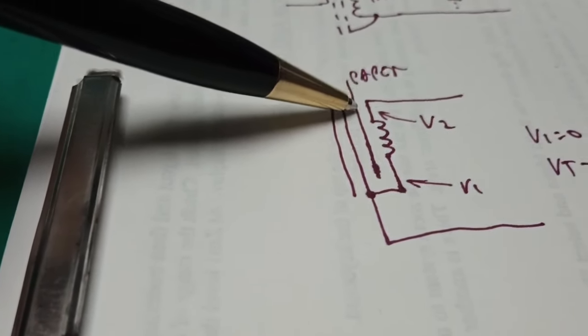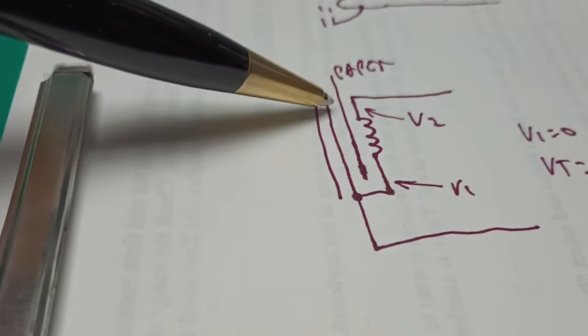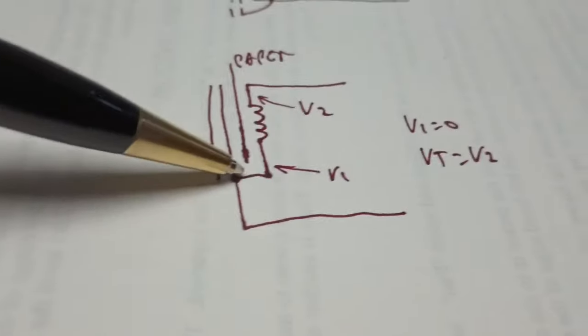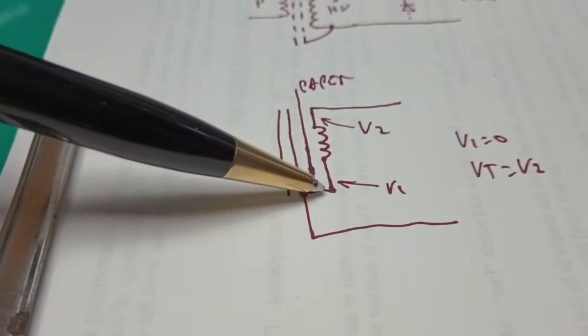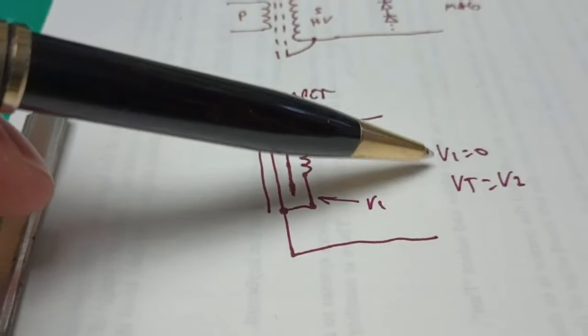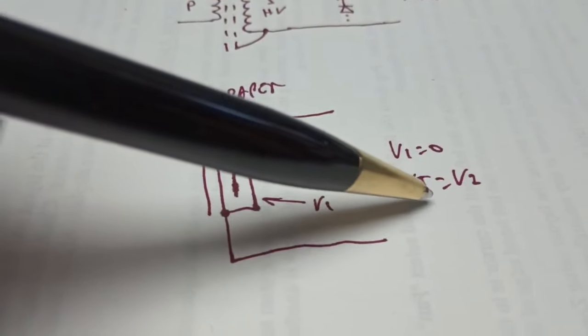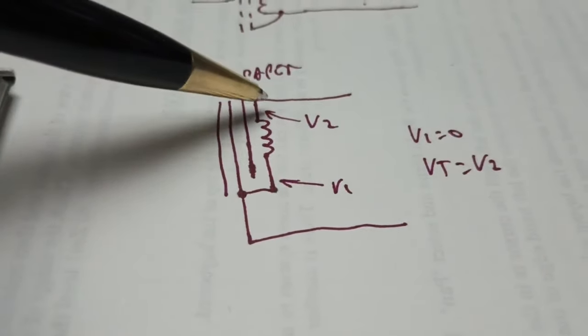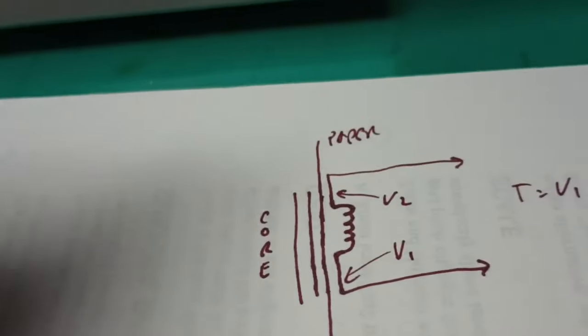So there's a voltage potential from here to here because of this connection with the other end of the winding. The winding potential is from here to here. The paper isolates and insulates this what I've termed V sub 2 from the core. The core is at V sub 1. So the difference in voltage between this end of the winding and the core, which is V sub 1, is 0 because it's a short circuit. That puts all the voltage of that winding at V sub 2 between here and here. So the full voltage of the winding is being insulated by that piece of paper.